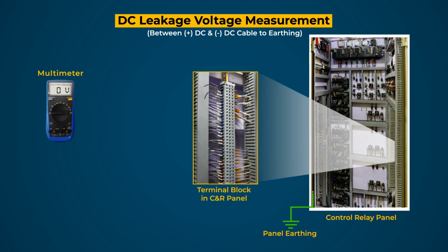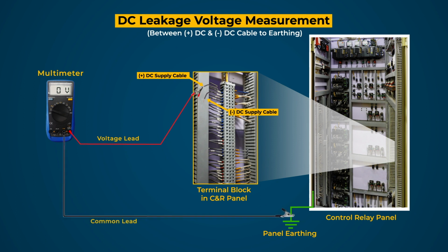Steps for testing. Here we are measuring the DC voltage between positive DC supply and negative DC supply to earthing in a control and relay panel. First, select the voltage scale in the multimeter. Connect the voltage terminal of the multimeter to one terminal of the positive DC supply terminal and connect the common terminal of the multimeter to earthing terminal of panel. Finally, multimeter shows the magnitude of DC supply in control and relay panel.